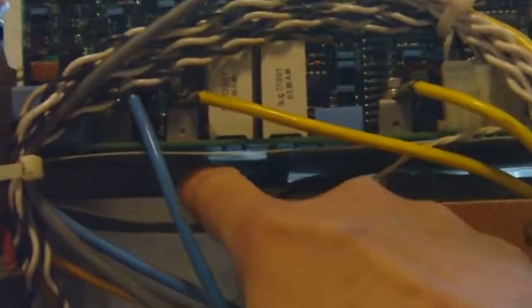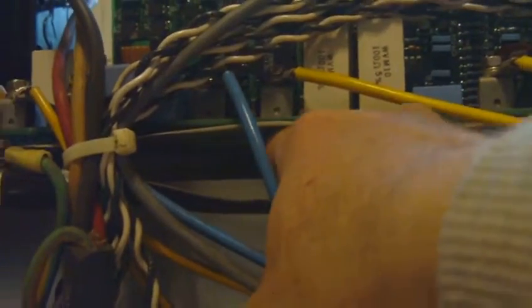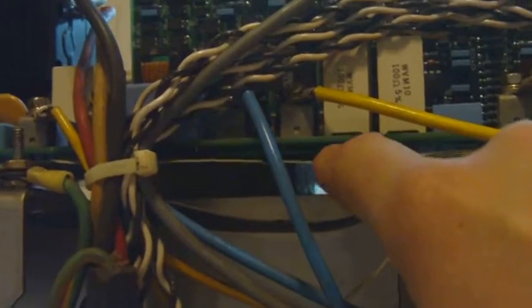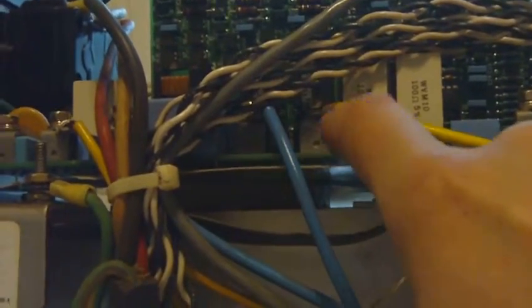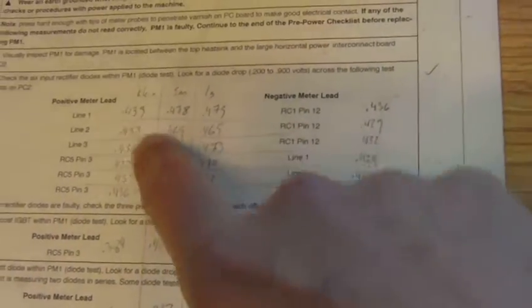Anyway, first up was the power control module, which is hidden down here. It's a little hard to see, but it's inside of this white block underneath this insulating screen and below the interconnect board. It's actually attached to this heat sink. Mainly what the power control module does is rectify the incoming voltage, create a DC voltage, and output it to the rest of the machine. So mostly what's involved there is checking the diodes.